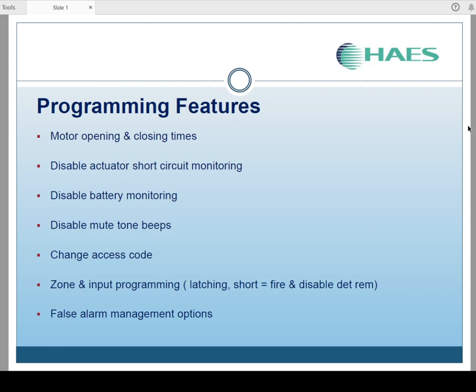You can disable the battery monitoring if you want to run this panel from some external charger. You can disable the mute tone, so by standard, if you have a fault and you hit the mute, the panel will beep every 8 seconds. With this programming function, you can turn it off so when the system's muted, it stays muted until a new alarm comes in. You can change the access code for your customer. Default is 1234. You can then also do zone and input programming.